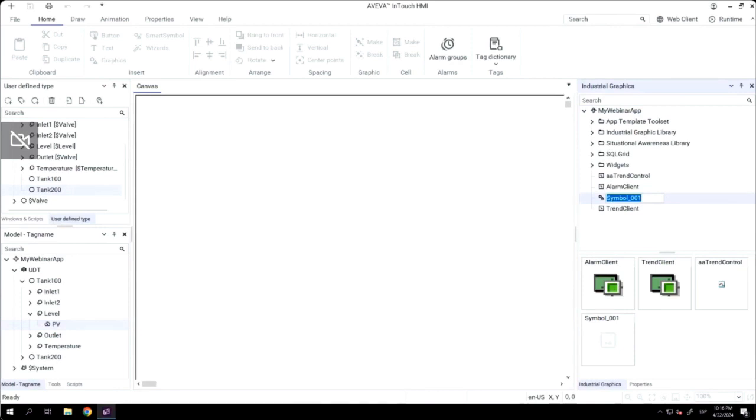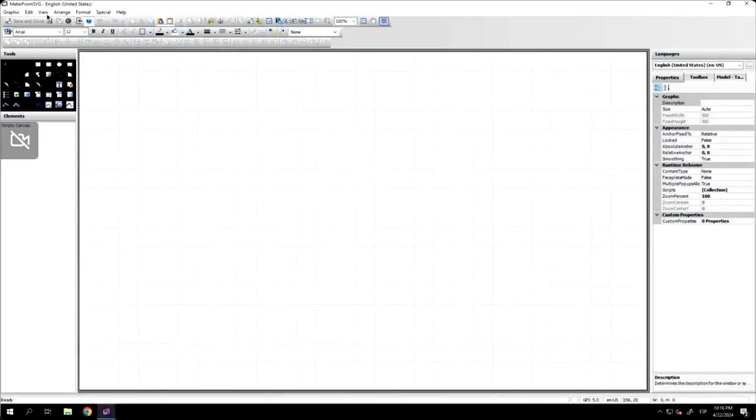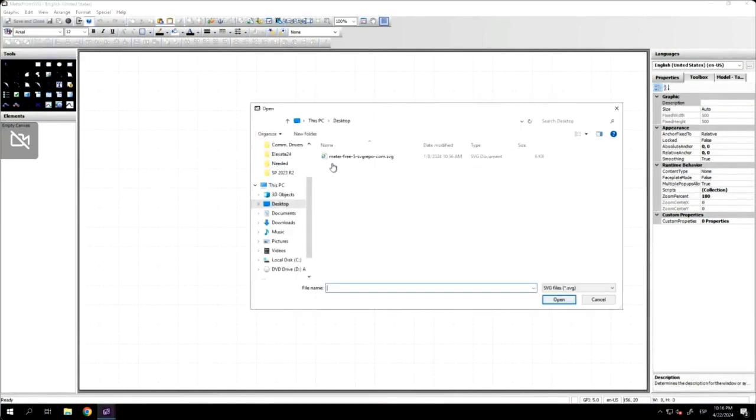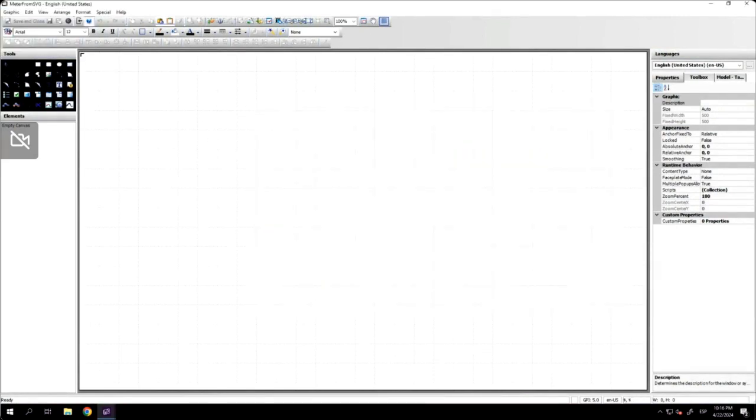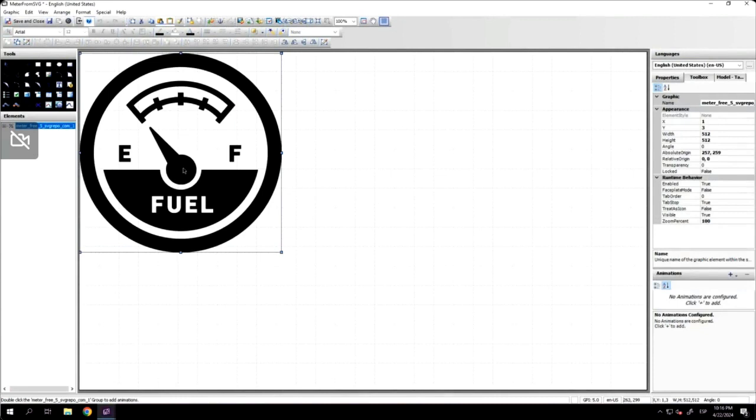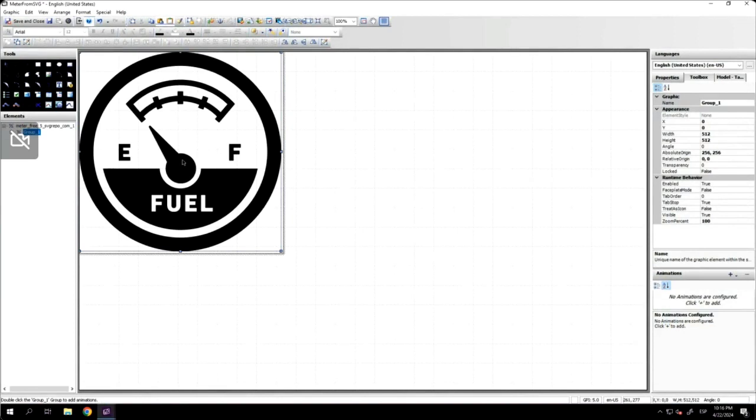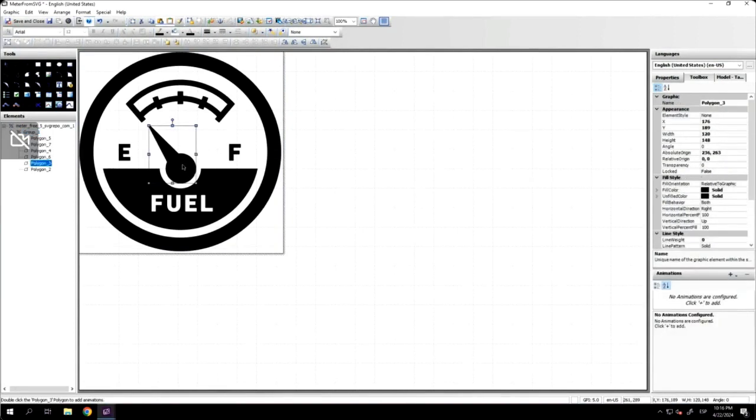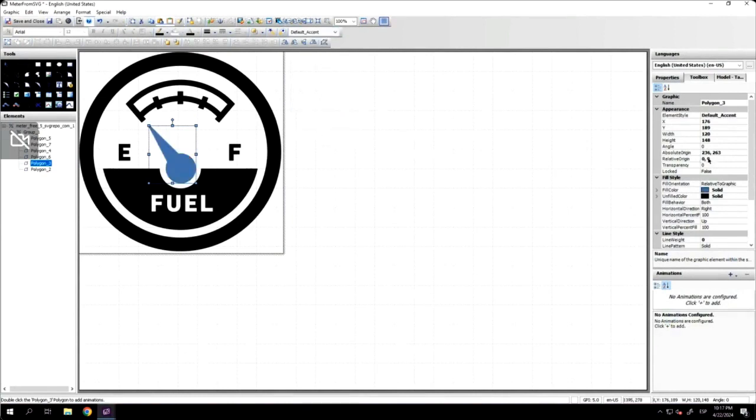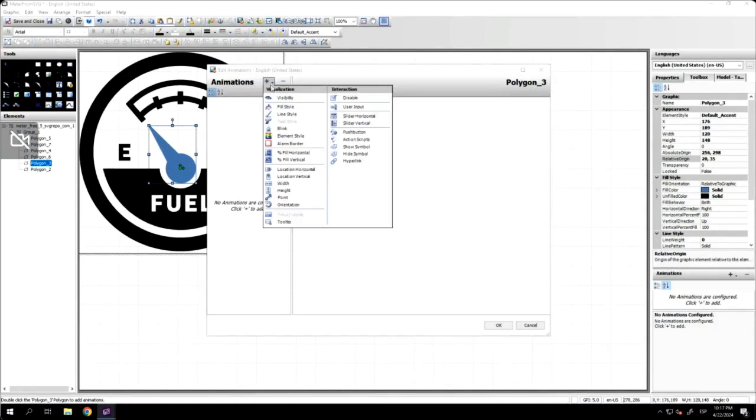Now, I will show you how I can create a custom graphic. I will create a graphic from a SVG file. This is why the name of this graphic is meter from SVG. First thing is I need to import this file, and the system will proceed and convert this graphic into an industrial graphic. Right now, I can modify any of the different elements. All of these elements are individual elements. I can change the color. I can change the relative origin. I can add animation. If I want, I can delete some of the parts. I can add new parts. I can do whatever I need.